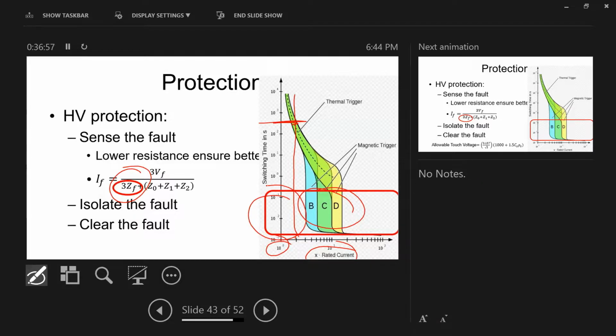If it tripped very fast, what does it do? We reduce the amount of energy caused by this fault. Remember, the electric energy is watt-hour. It's not the instantaneous power. That's very critical for us to determine. So our circuit breaker that has taken this massive load, I needed it to trip in a small amount of time.